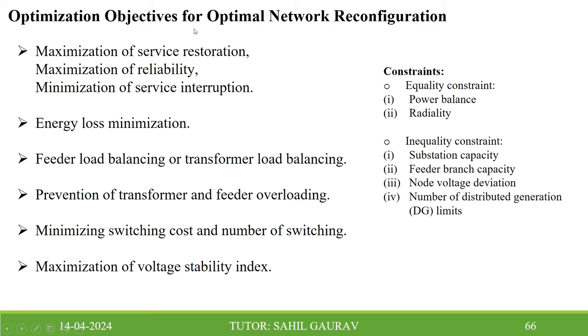Now, what should be the optimization objective? What can be the optimization objective for optimal network configuration? These can be the objectives: maximization of service restoration, that is, maximization of reliability or minimization of service interruption, energy loss minimization, feeder load balancing or transformer load balancing, prevention of transformer and feeder overload, and so on.